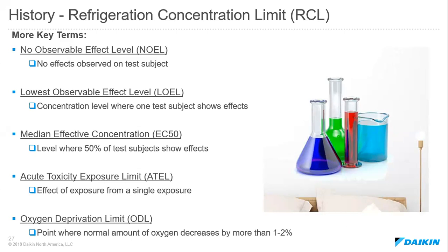Lowest observable effect, which is the concentration level where one test subject shows effects. The median effective concentration, which is a level where 50% of the test subjects show effects. Acute toxicity exposure limit, which is the effect of a single exposure. And then finally, the oxygen deprivation limit, or ODL, which is the point where the normal amount of oxygen decreases by more than 1 to 2%.